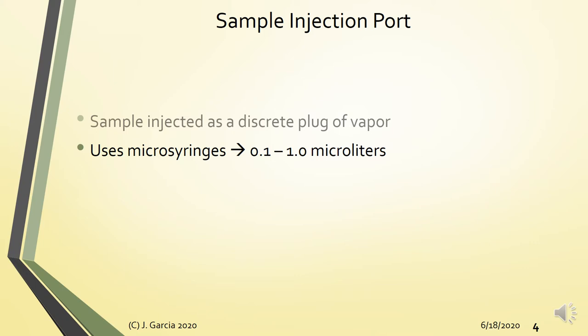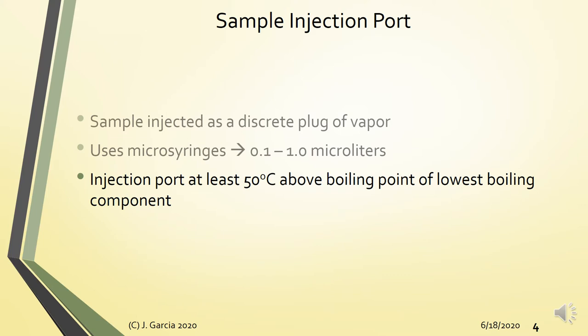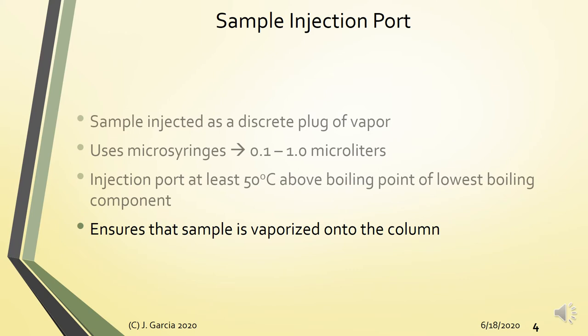There are also gas syringes for gaseous samples, which have larger volumes compared to liquid microsyringes. The injection port temperature is high enough to vaporize the sample, since it is important that the sample is in vapor form when it enters the column. Normally the injection port is set at least 50 degrees Celsius above the boiling point of the lowest boiling component in the mixture, to ensure the sample is completely vaporized before entering the column.